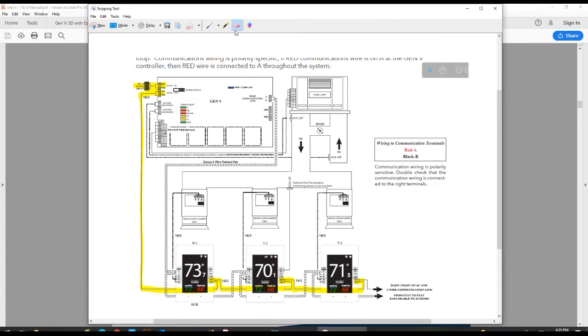When wiring, try to minimize any wire nuts or butt connectors. We want to have nice clean splices. This in turn helps reduce any potential for voltage drop or loss. Now on the communication side of the system, we use RS-485 communication. So we have supplied you with the Zonex twisted pair wire that we spec for our controls. Utilizing this wire, you will wire it into the A and B terminals and daisy chain that to and from each zone thermostat as well.